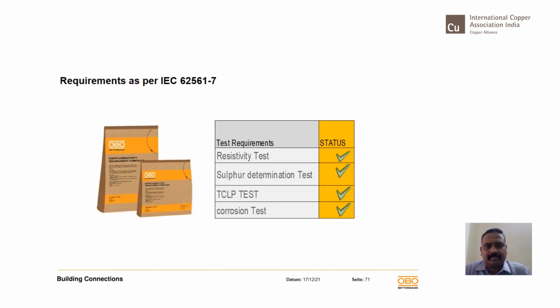When it comes to compound, whatever material you want to use, you are free to use, the standard does not stop you. However, the 4 tests have to be passed: toxicity characteristic leaching properties, corrosion test, sulfur determination test, and resistivity test. If the compound passes these, it is free to be used along with the electrode.